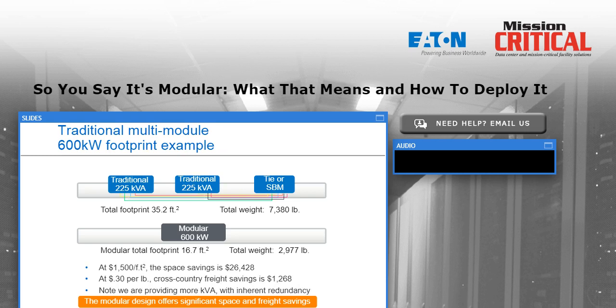Here's an example of some of the benefits of using a modular UPS system. In the top part of this slide, we see a client that has a requirement for N+1 redundancy, and they've deployed it in the conventional manner that's been done for probably 40 years. They have a critical load that's in the range of 200 kVA. So they've deployed in the blue blocks there 2 225 kVA UPSs with a tie cabinet or SBM or system bypass module to tie those 2 independent UPSs together.